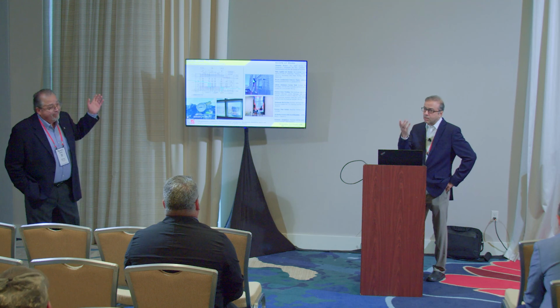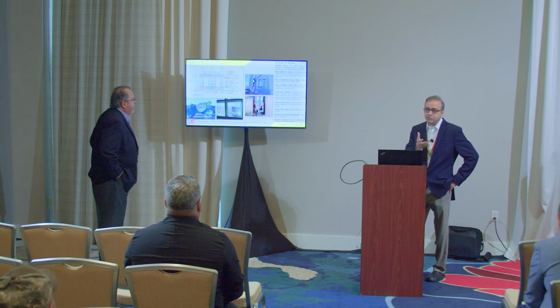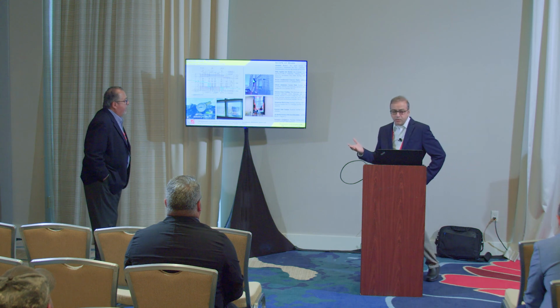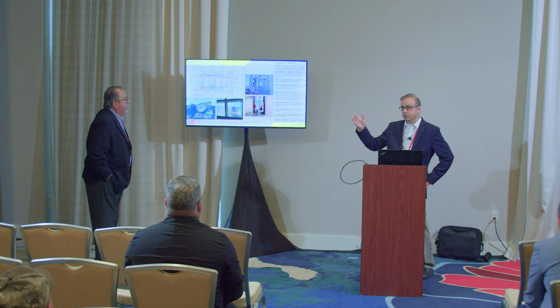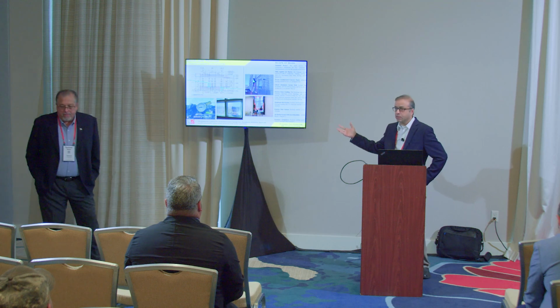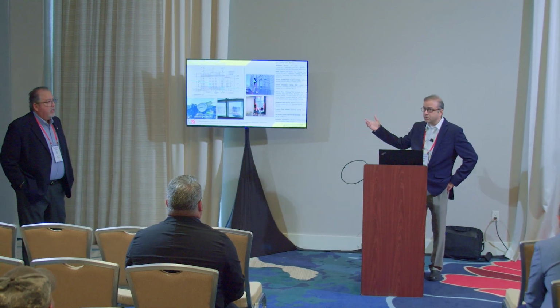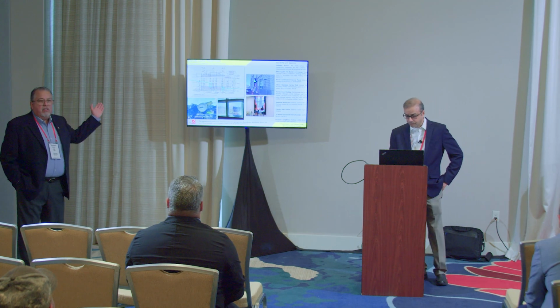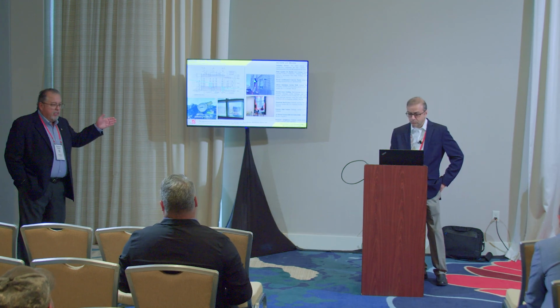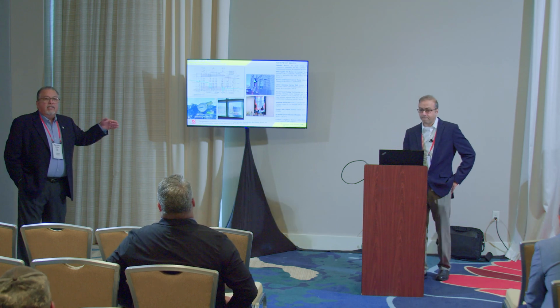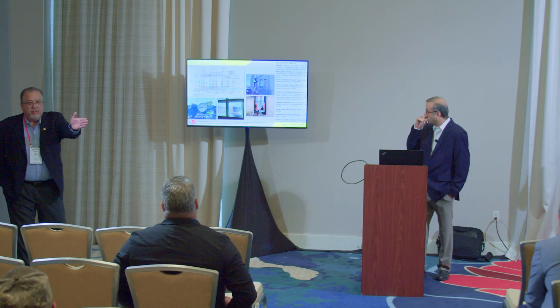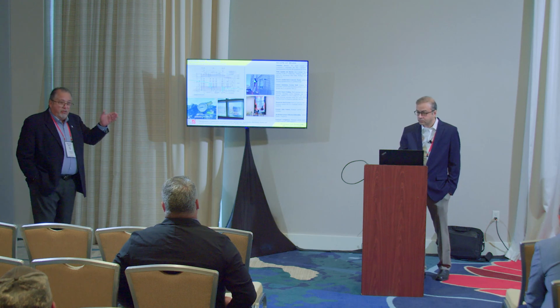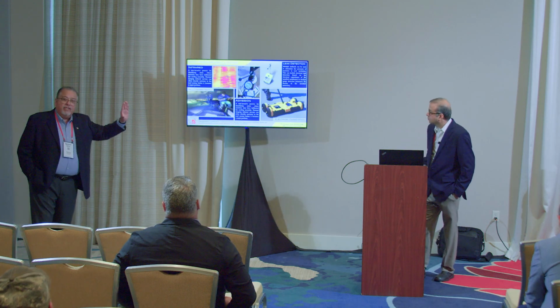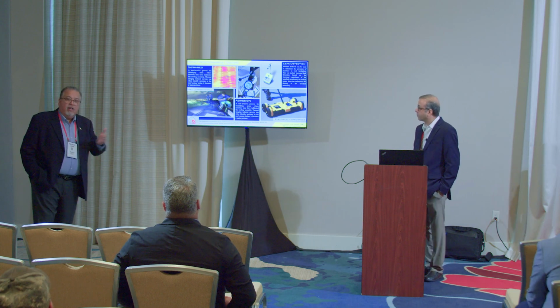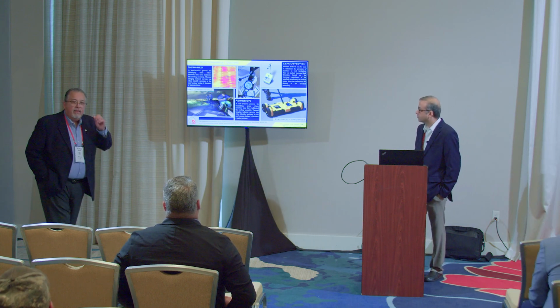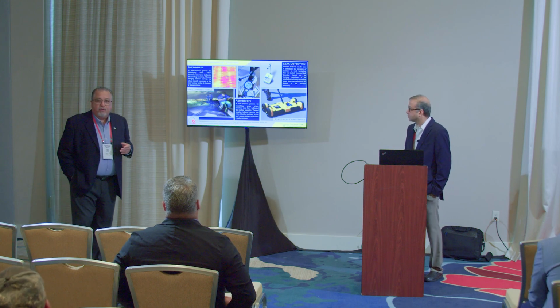The key is during the specifications stage, work with the team and do this testing at 10% completion, 50%, and so on, so if there's an issue caught at 10%, it saves everybody. That all comes down to the commissioning plan put together by the commissioning agent, who schedules tests at 10%, 50%, 80% completion, making sure that as construction progresses, problems that aren't being done correctly are fixed.